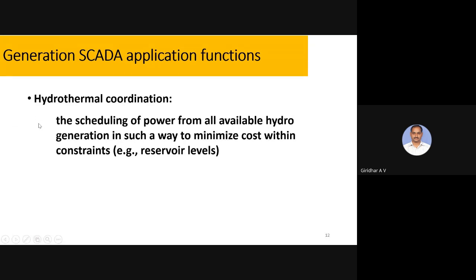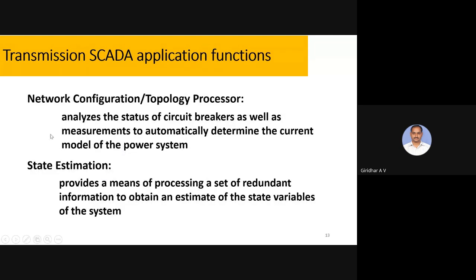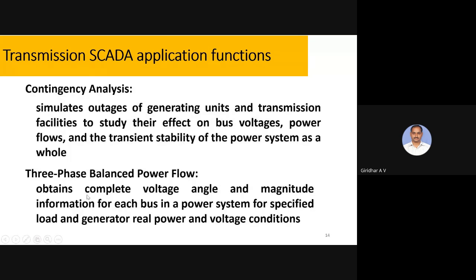Hydrothermal coordination, like scheduling of power from all available hydro generation, tries to minimize the cost. Transmission SCADA applications include network configuration and topology. From the transmission, status of circuit breakers and measurements can all be collected automatically. State estimation can also be done: if there is some error in the CT or PT measurements, it can be corrected with state estimation and analyzed properly.